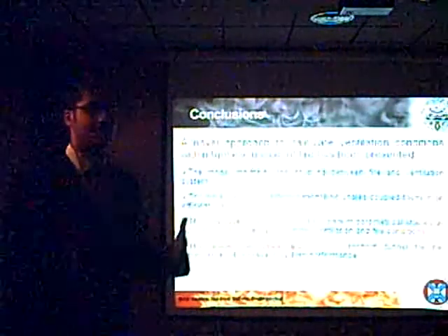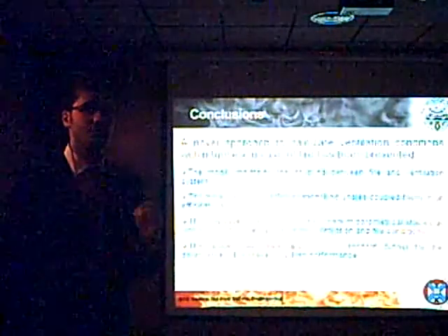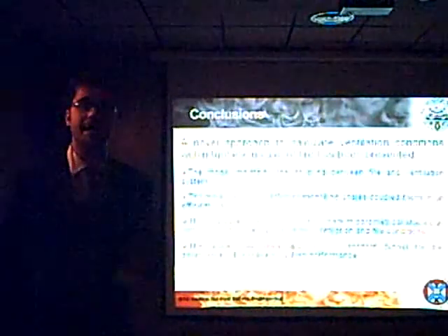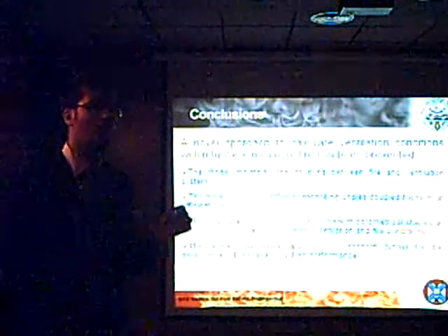So in this work, we present a novel approach to calculate the ventilation condition within the tunnel. The model is able to maintain the coupling between the fire and the ventilation system, so we are able to see how the fire and the ventilation system affect the final ventilation condition within the tunnel. The model uses two different scales to treat the fluid dynamic problem: a one-dimensional scale in the region where the flow behaves one-dimensionally, and a CFD model when we want to represent the fluid behavior close to a disturbance.